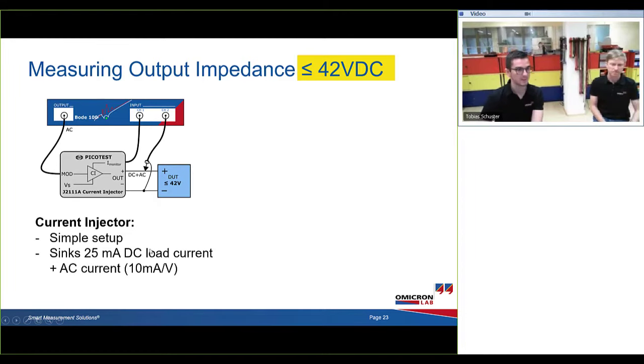Here you can see the measurement setup using the PICOTEST current injector. There is the modulation input where the Bode 100 is connected, a current monitor to measure the current that is drawn from the output of the VRM, and then you have channel 2 where you measure the voltage. Then you have a voltage and the current signal where you get the impedance. The setup is very simple. We will also show that afterwards in a short example on live measurement.